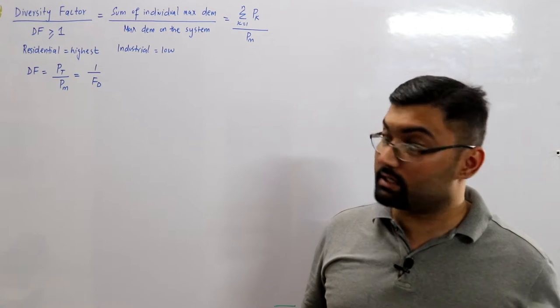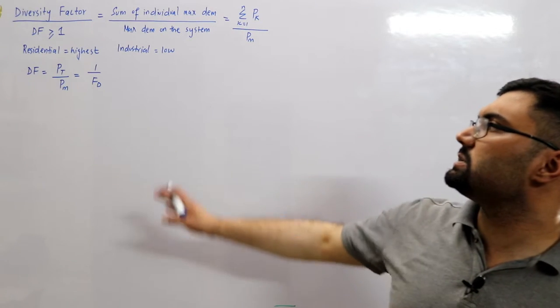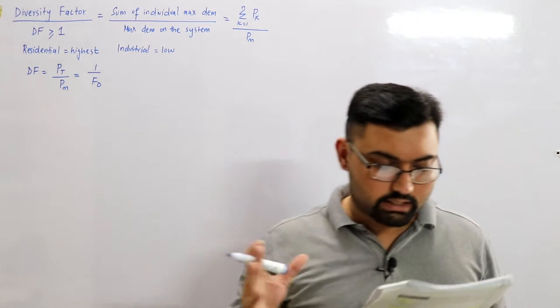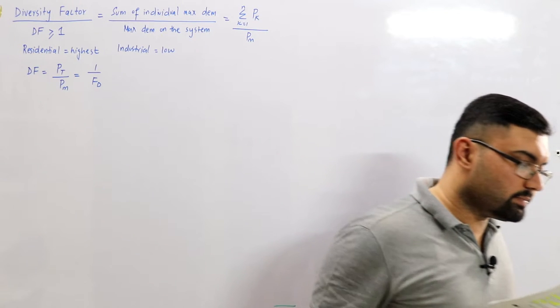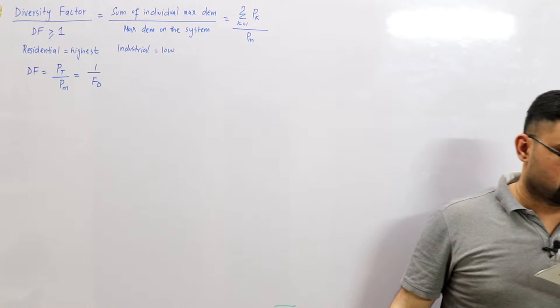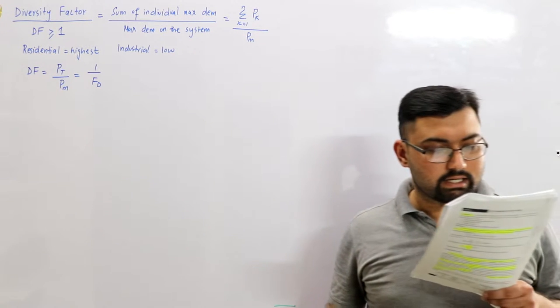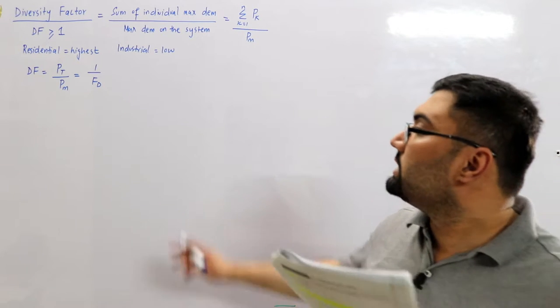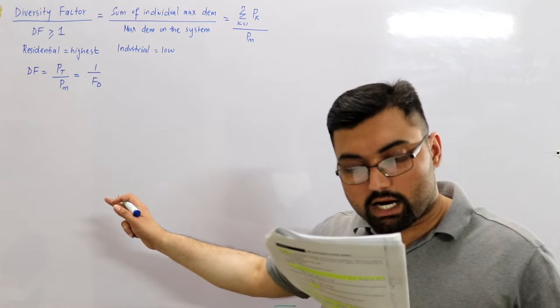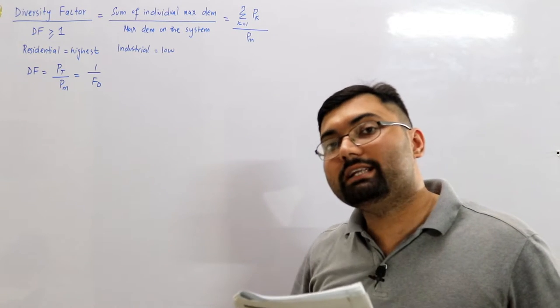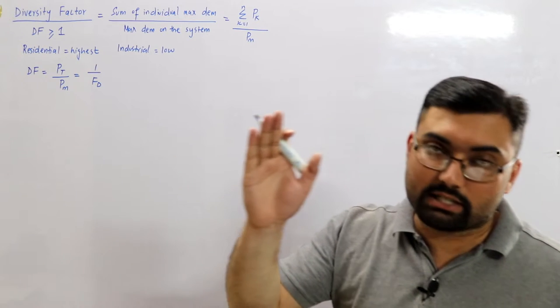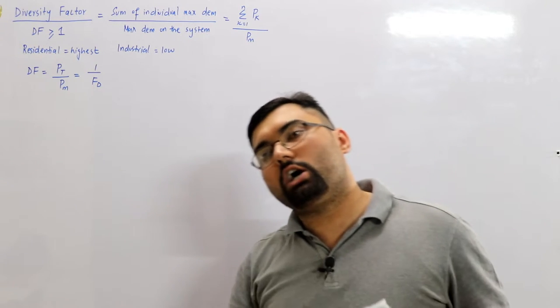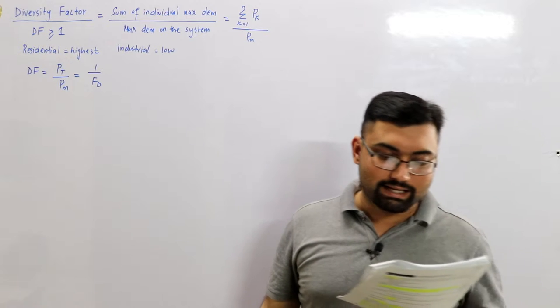Field experience can justify using unity. Many designers prefer to use a diversity factor of 1. The greater the diversity factor, the lesser the maximum demand, meaning the plant capacity will be less and hence the capital cost of investment would be less.